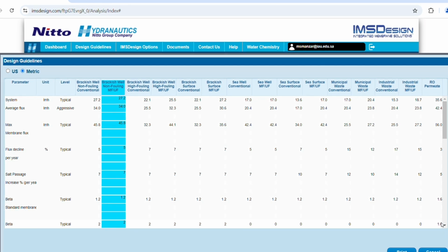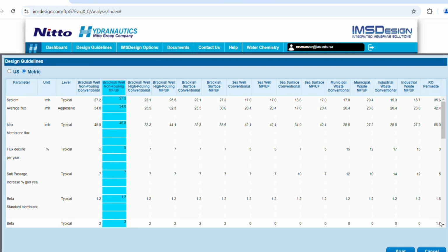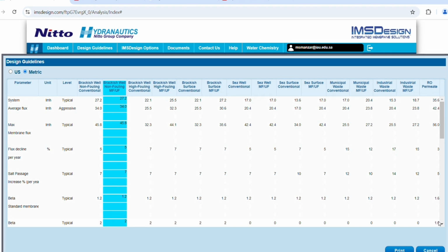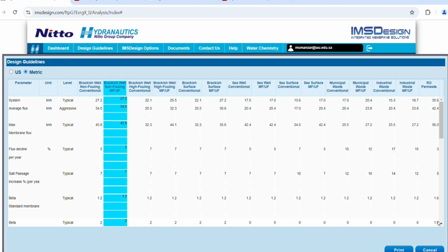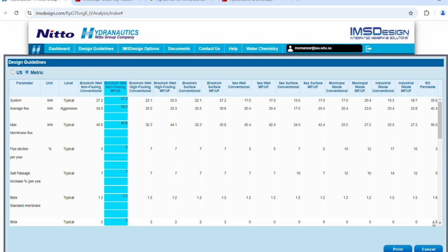When we say high flux, it means higher pores, which will allow the diffusion of a great amount of pollutant. The flux range for a membrane, for practical applications, lies between 50 and 200 GFD, and the operating pressure is about 50 psig. For reverse osmosis it lies between 10 to 30 GFD. For calculating the membrane flux, we divide the permeate flow rate by the membrane area. Whatever permeate flow rate you put in, you divide by the area.